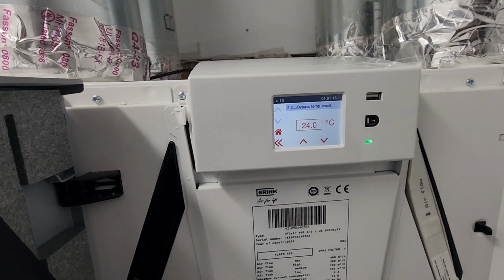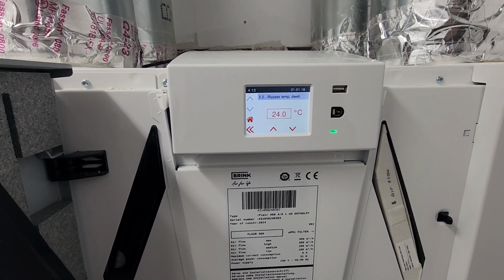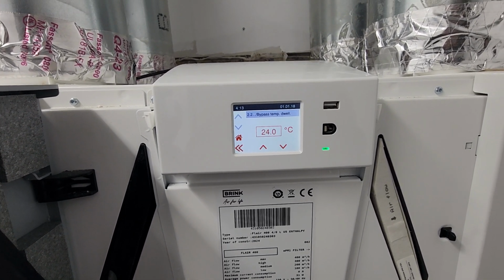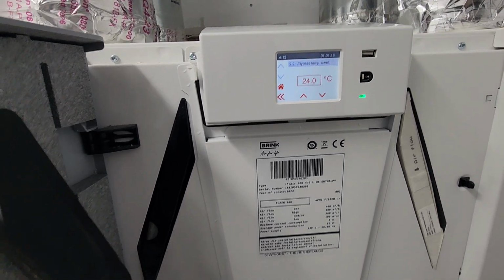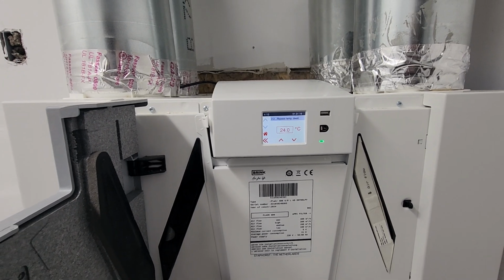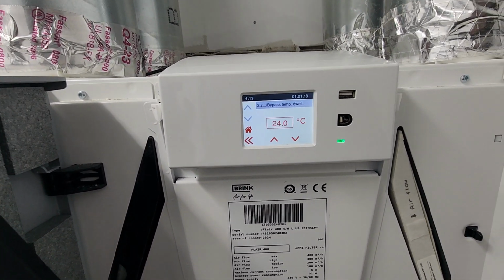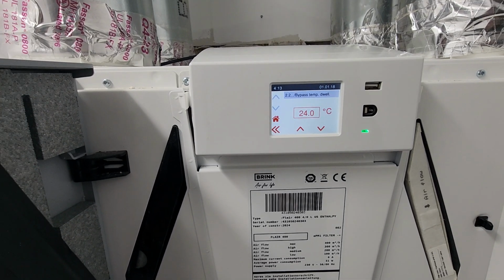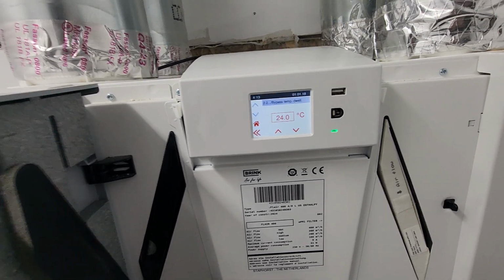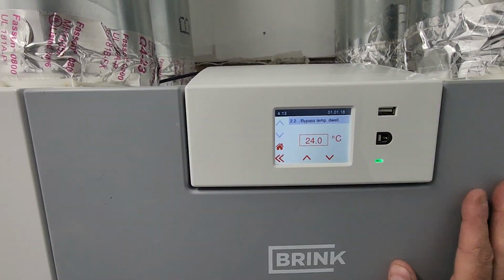So it's going to take fresh air from the outside that's colder, and it will bypass the heat recovery core and go straight into the house. So at nighttime, especially in the summertime, we're going to be able to get free cooling, essentially, when the house gets over 75 degrees. So that's a really cool option, very easy to program, no muss, no fuss.